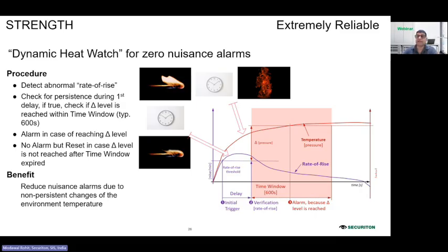If you talk about the false alarm immunity, we have an extremely reliable system which has zero nuisance alarms because we use Dynamic Heat Watch technology. There is an algorithm already built in, so it continuously monitors temperatures, and even the temperature changes along the sensing tube are monitored continuously. It automatically adapts sensitivity to the environment.